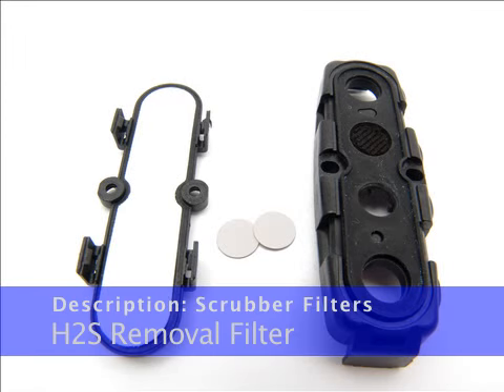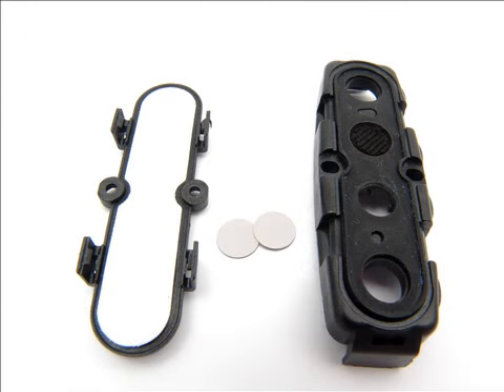2 H2S removal filter discs are located in a recessed area of the combustible gas sensor diffusion port in the sensor retainer. The H2S removal filter discs are white when new. They scrub hydrogen sulfide out of the gas sampled to increase the life of the combustible sensor. They darken as they absorb H2S and must be changed when they turn to a dark brown color. The recommended replacement frequency will depend on how often the unit is exposed to H2S and the concentration. Check the condition of the H2S removal filter discs quarterly.